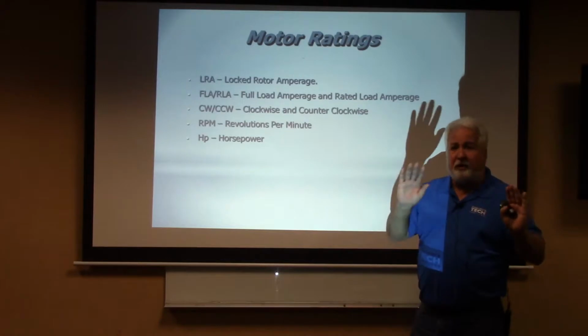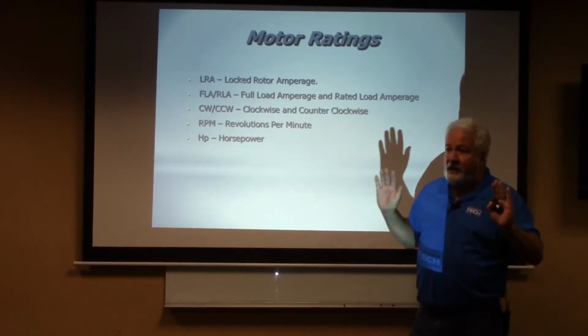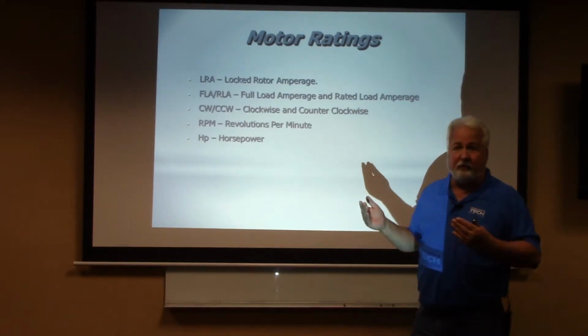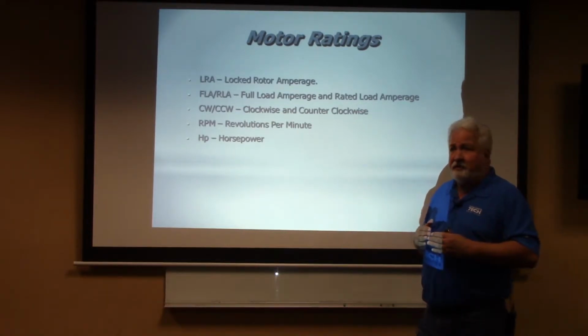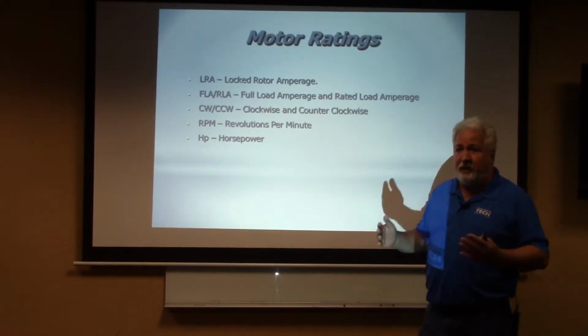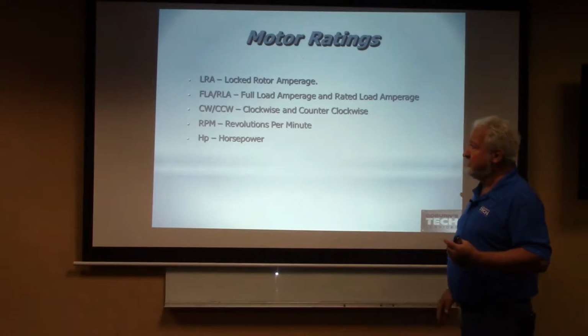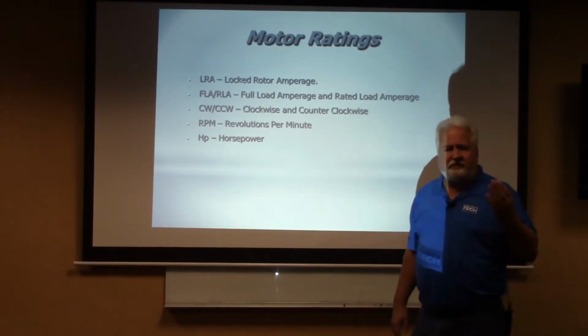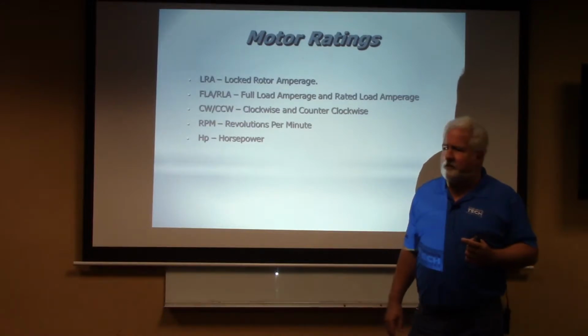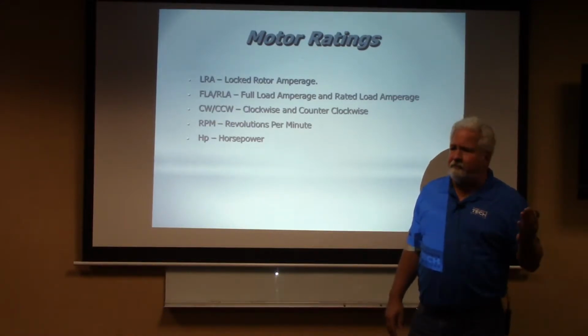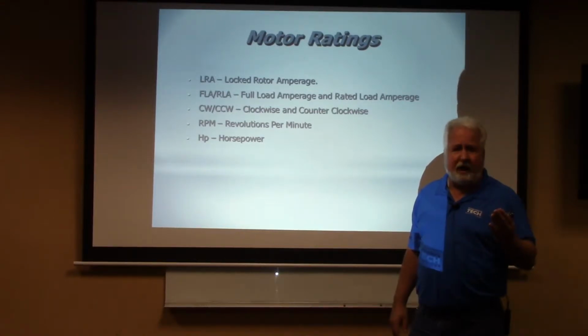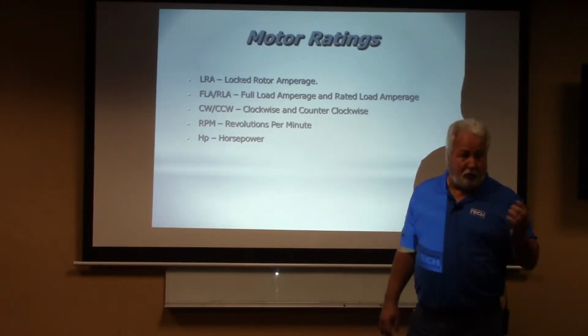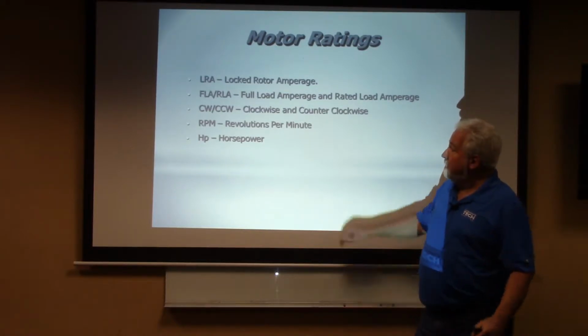That way the different motor and compressor manufacturers can all rate their compressors at the same rating, where they can get the output for that compressor. Does that make sense to you guys? Because otherwise I could just change the voltages and get my amperages to drop down very easily. So rated load amperage: can I operate outside of rated load amperage? If it's rated at 95 degrees at 240 volts, can my compressor sometimes operate higher than rated load amperage? Quite possible you could be outside of rated load amperage. It doesn't necessarily mean that the compressor is bad. It does mean that it's operating outside of rated load, or what the rating was set up for. Everybody good with that? Good.